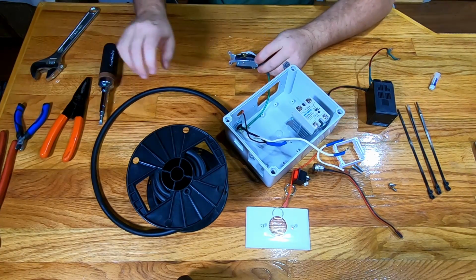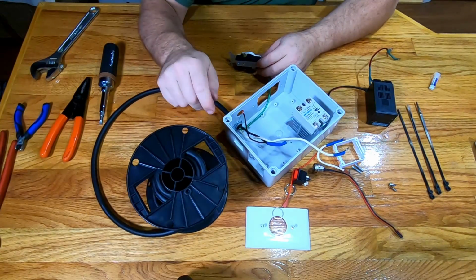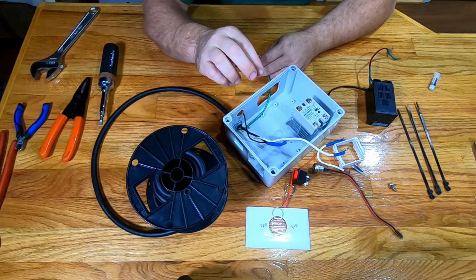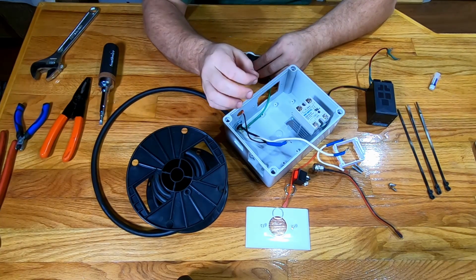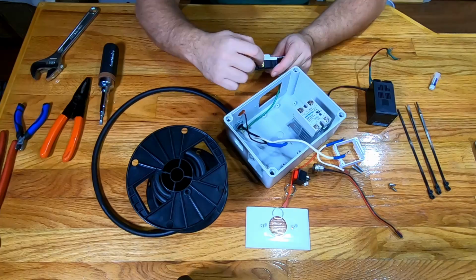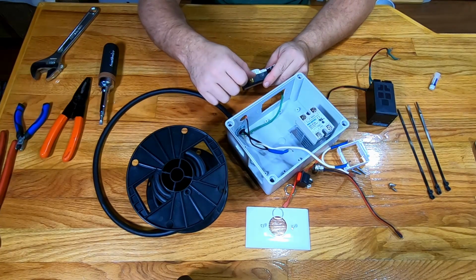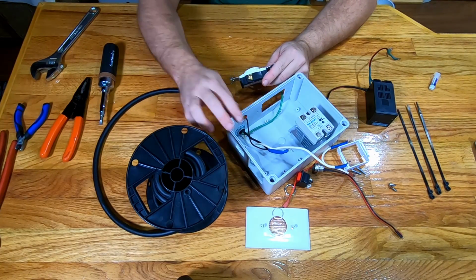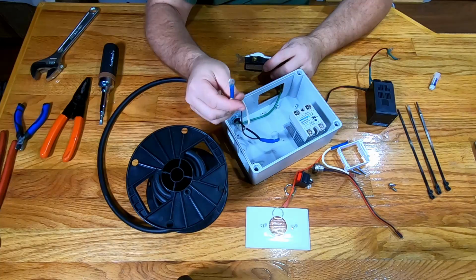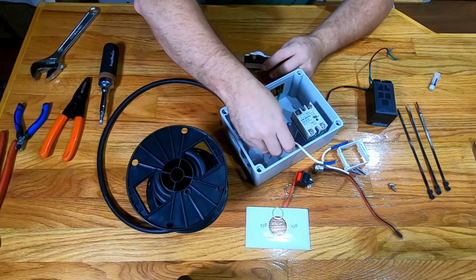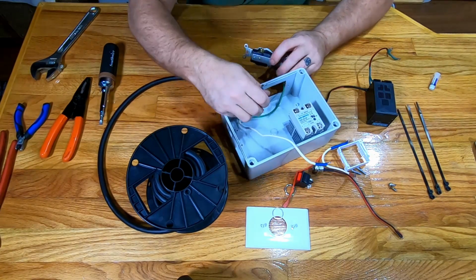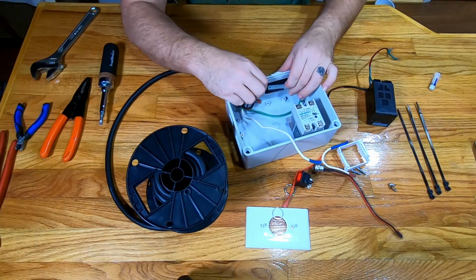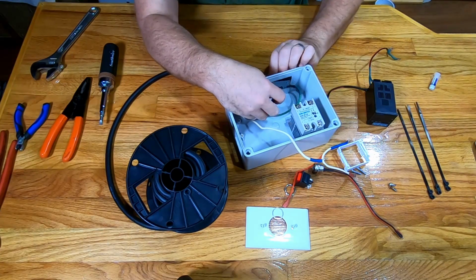Now, normally on a receptacle, you can just put the wire around the screw and tighten it down. But since this SOW cord is stranded wire, I didn't want to try to wrap the strands around this and tighten it down and not get a good connection. I wanted to use the actual crimp-on connectors and solder those in place, then heat shrink them to seal them so we don't have to worry about it coming loose at any point.